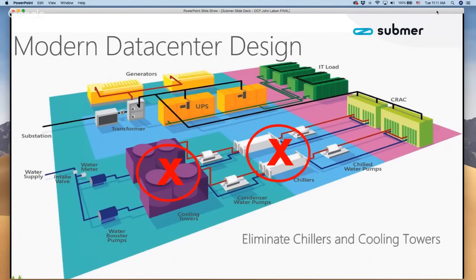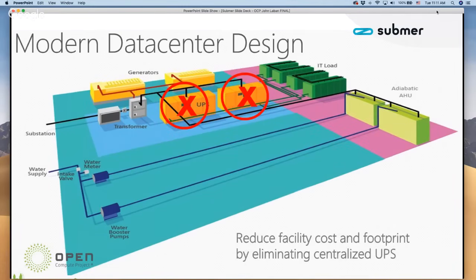If we look at the next slide, you'll see what we do as well — we optimize the data center by removing the centralized UPS. I'll show you some schematics in a minute to demonstrate the impact this has on energy efficiency. But there's also another issue with centralized UPS systems: it creates a major failure point, even with dual redundant systems, and it's often where you'll see the major problem related to that centralized UPS function.